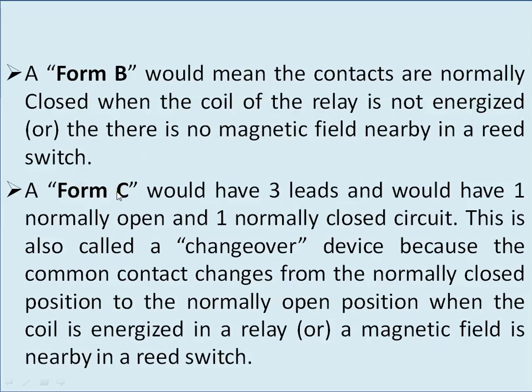For Form C, the contact relay or switch has three leads — one normally open contact and one normally closed contact. This is known as a changeover device, because whenever the relay or switch is energized, the contacts will change over: NC will become NO and NO will become NC.